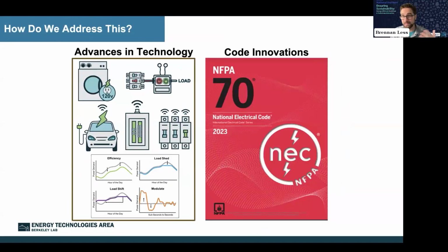So what do we do about this? Alex covered a bunch of currently available ideas, but we still need more advances in technology, right? Things like communicating and battery integrated appliances, load controls, the ability to do load shedding, load shifting, modulation, all these ideas where we can manage our capacity. Part of that is managing the actual demand of a dwelling and making sure it doesn't exceed safety thresholds. And then the other part is just getting an acceptable load calculation based on our electrical code.